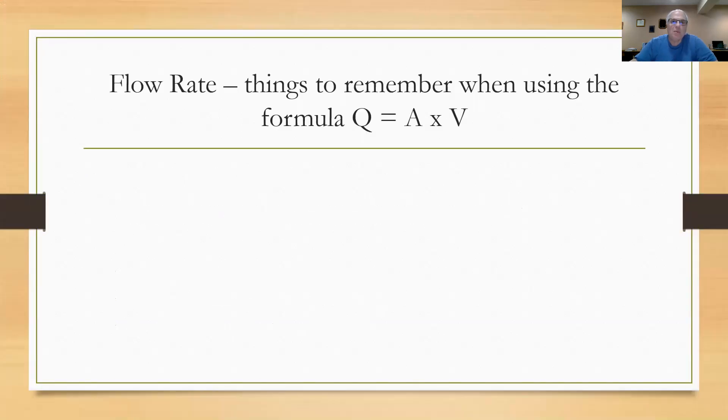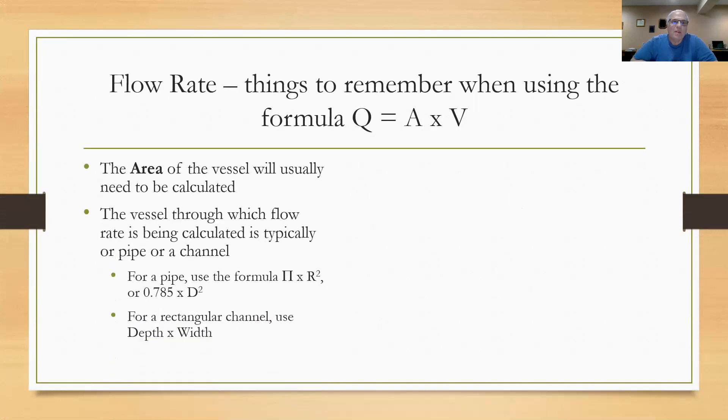So here's some things we need to remember when we do Q equals A times V. The area of the vessel usually needs to be calculated. In the last example I gave you, I went ahead and calculated the area beforehand, but normally in a problem they give you, you're going to have to calculate the area. The vessel through which the water is flowing is typically going to be a pipe or a channel, and you're going to have to know the formulas to calculate the square area. For a pipe, it's pi r squared, or 0.785 times the diameter squared. For a rectangular channel, you use depth times width.